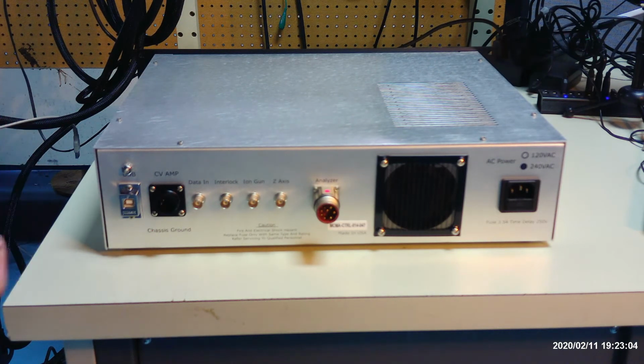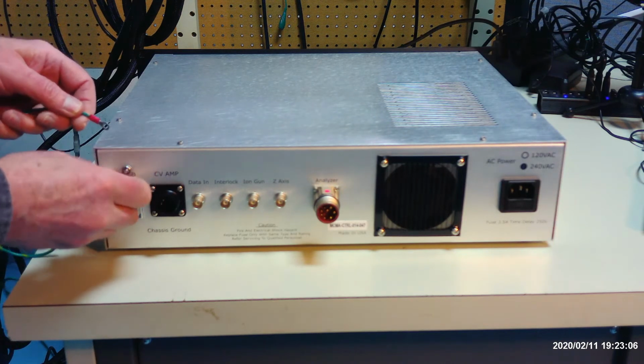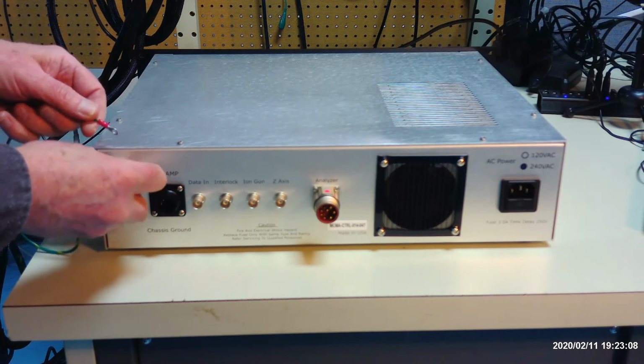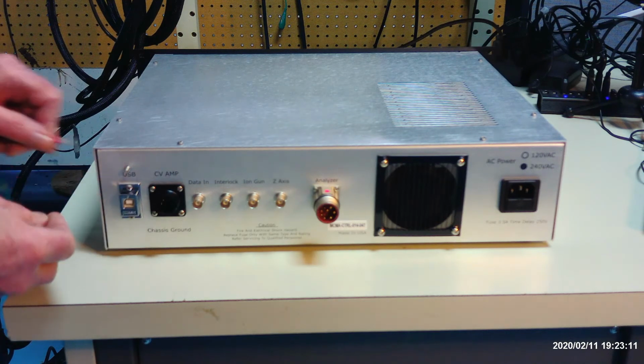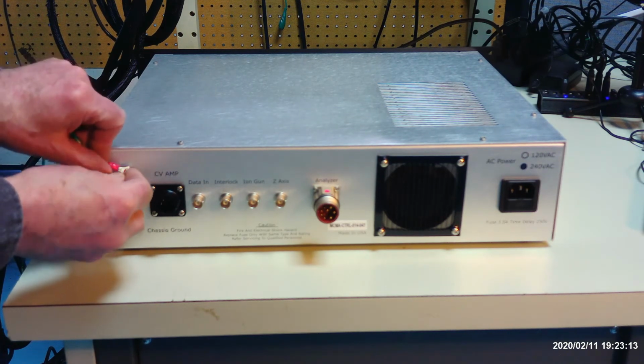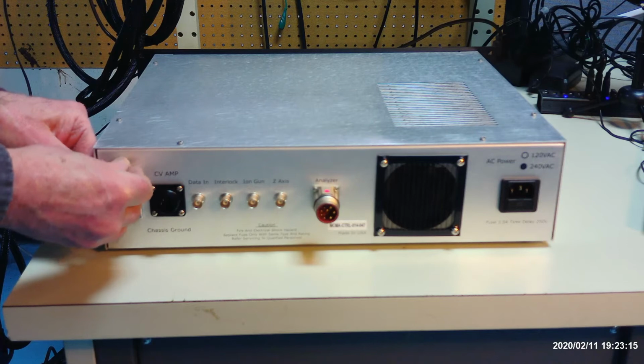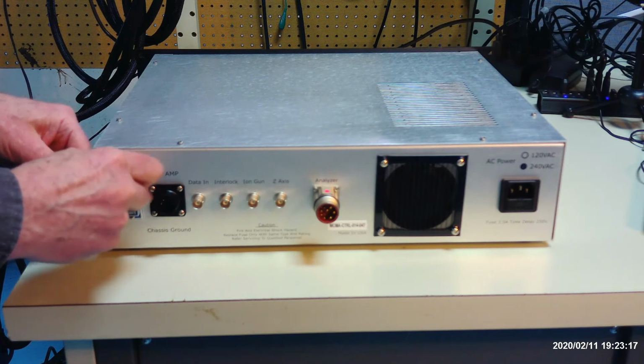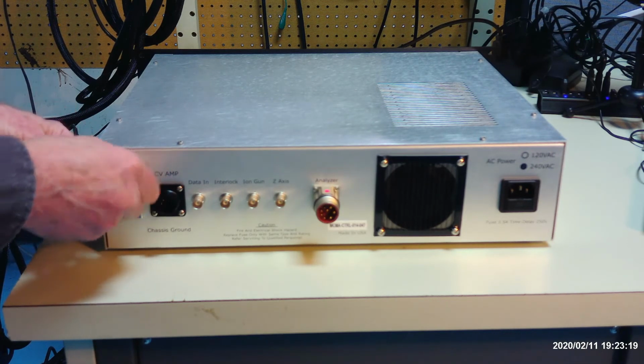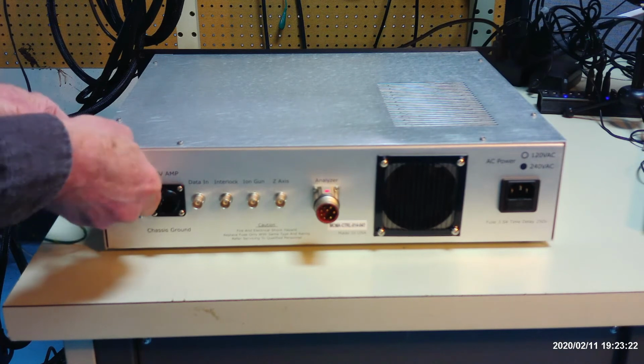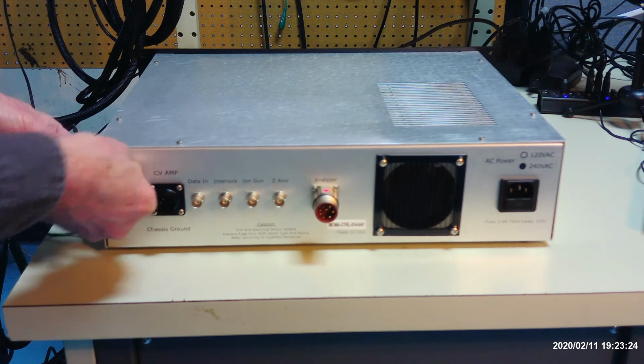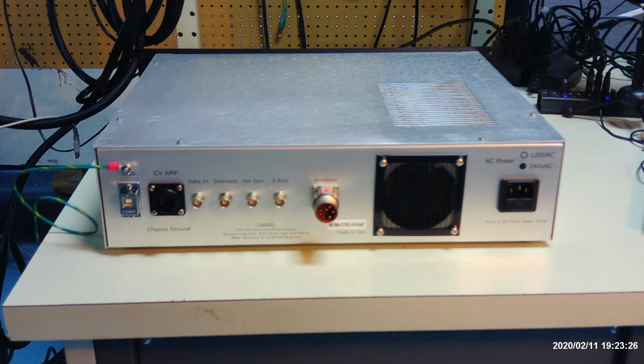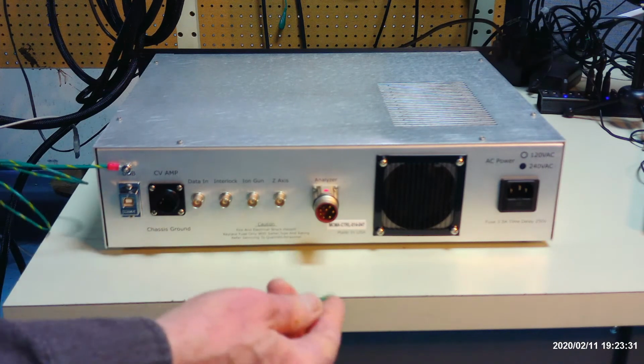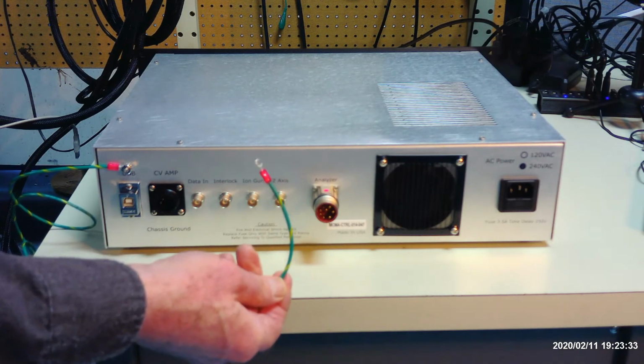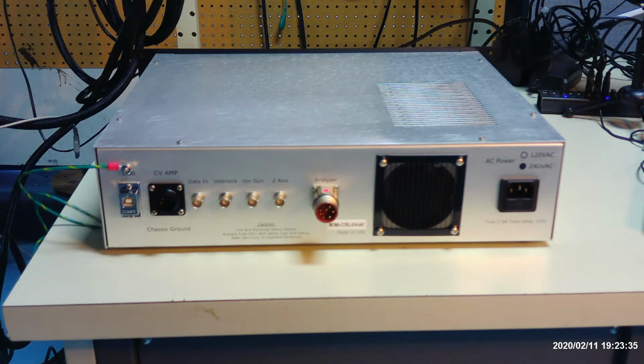So the first cable we'll connect is back near the USB connector in the back left hand corner, the ground connector. So we connect the ground to the back of the controller. You can tighten that up a little bit with a pliers or a wrench if you want. And then the other end of the cable will connect either to your vacuum chamber or to your electronics console, but we want to make sure that it's grounded.